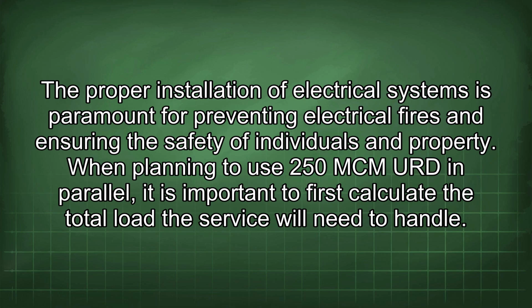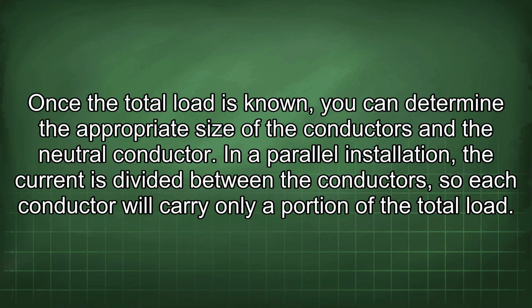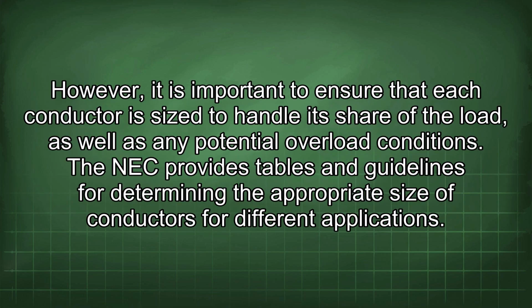When planning to use 250 MCM URD in parallel, it is important to first calculate the total load the service will need to handle. Once the total load is known, you can determine the appropriate size of the conductors and the neutral conductor. In a parallel installation, the current is divided between the conductors, so each conductor will carry only a portion of the total load. However, it is important to ensure that each conductor is sized to handle its share of the load, as well as any potential overload conditions.